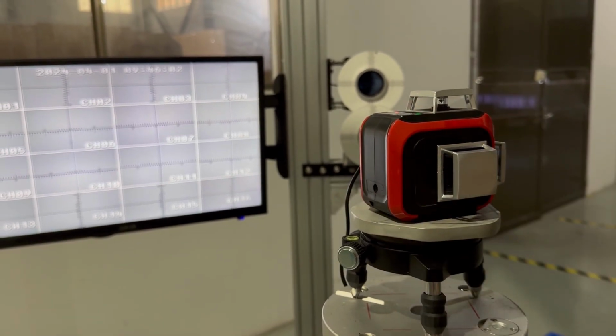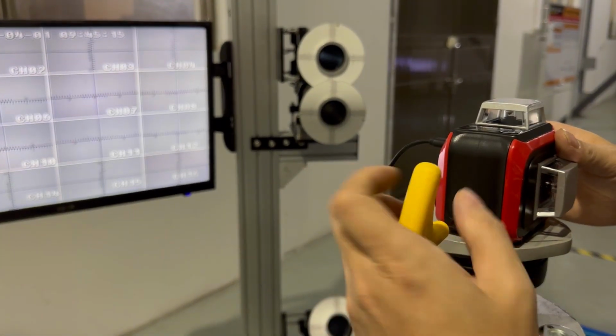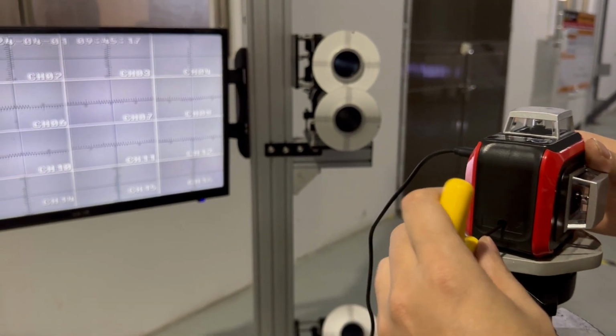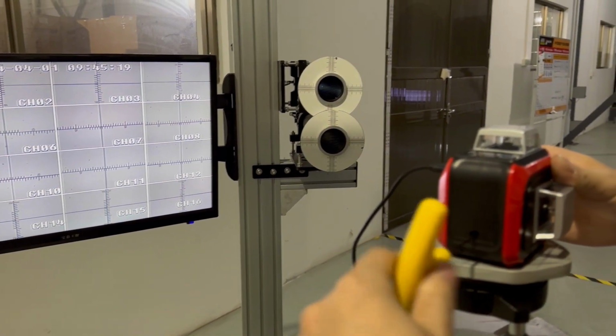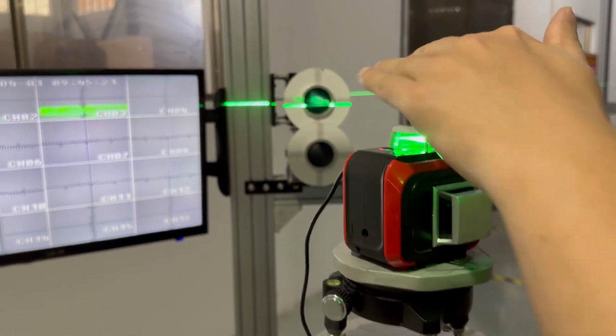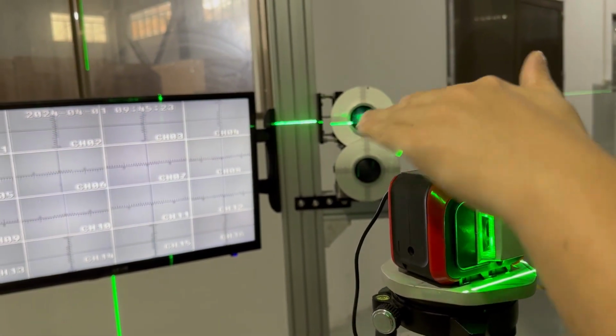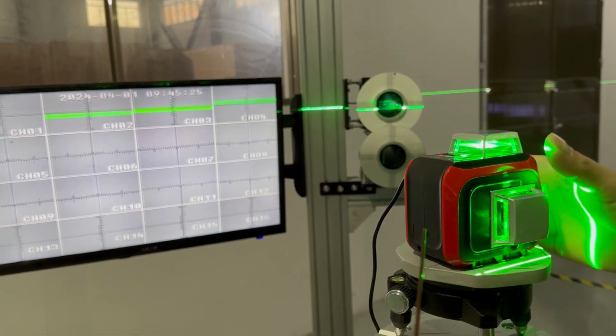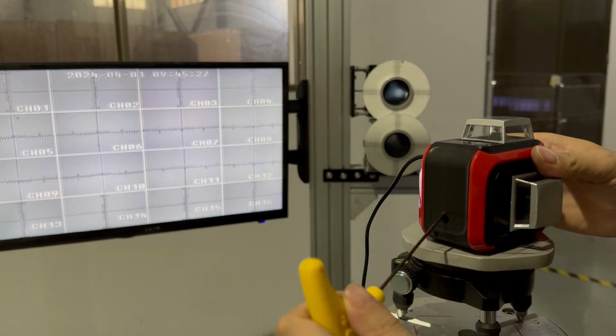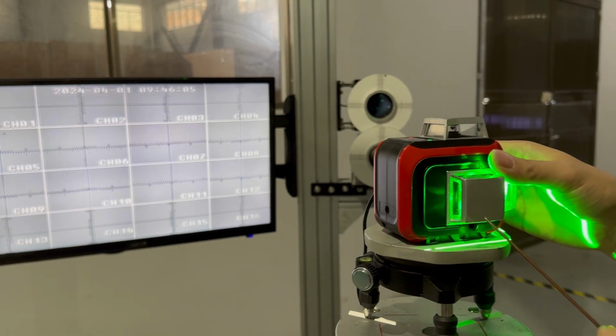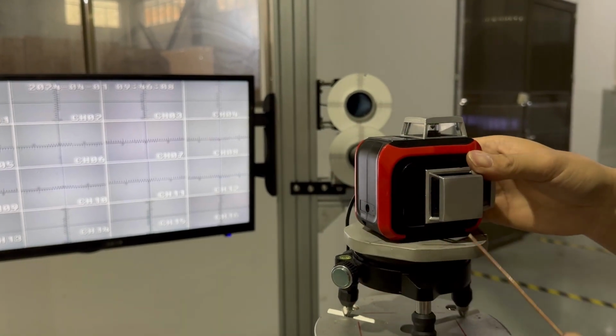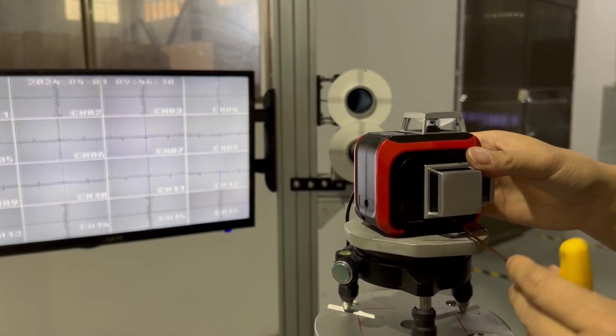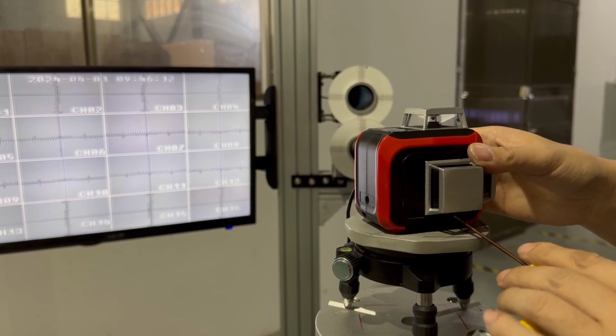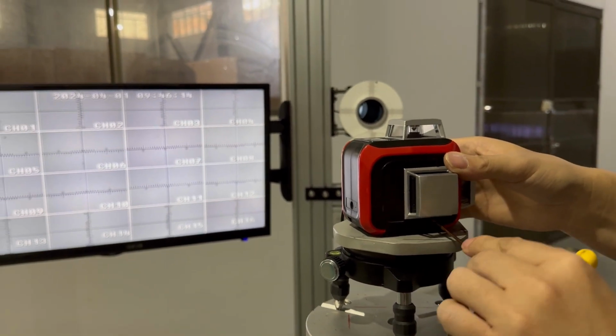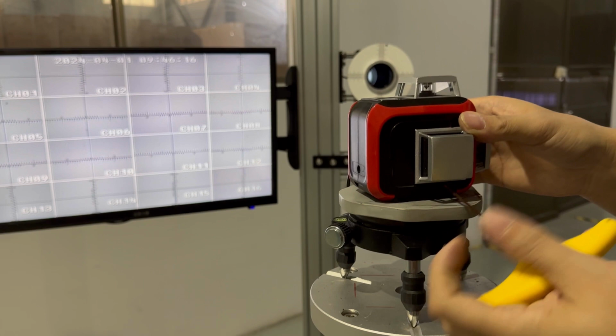So step 3. Use the Allen wrench to generally calibrate as your standard practice. Please take note, the access point located at the back of the unit is your control center for adjusting the horizontal dial's front to back accuracy. Meanwhile, the access point on the side, technically beneath the side frame, is responsible for the fine-tuning of the left to right accuracy of the same horizontal dial.